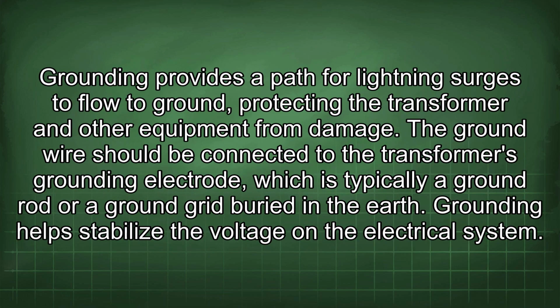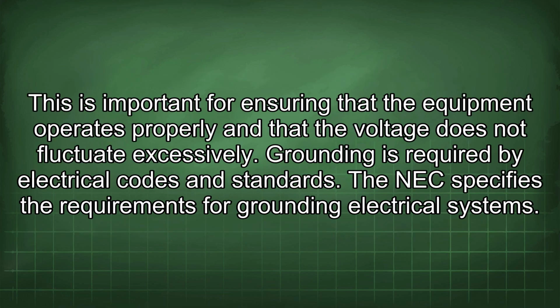Grounding provides a path for lightning surges to flow to ground, protecting the transformer and other equipment from damage. The ground wire should be connected to the transformer's grounding electrode, which is typically a ground rod or a ground grid buried in the earth. Grounding helps stabilize the voltage in the electrical system. This is important for ensuring that the equipment operates properly and that the voltage does not fluctuate excessively.